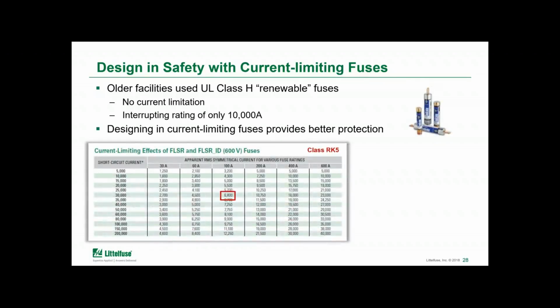Just to keep building on this, current limiting fuses do provide much better protection all around, and the different class fuses provide different degrees of current limitation. When you look at the tables provided by the manufacturer, you can see what type of current limitation you're going to get when you're looking to replace those fuses.